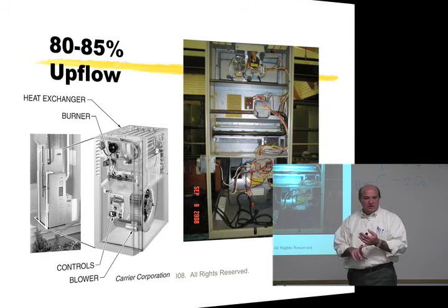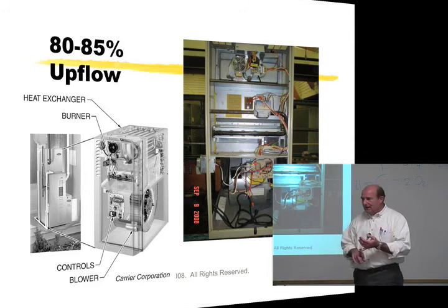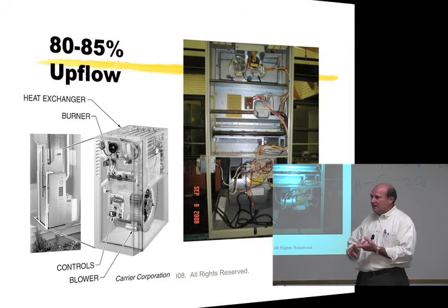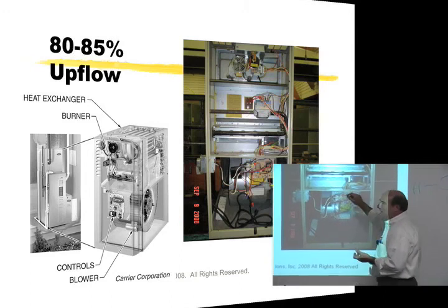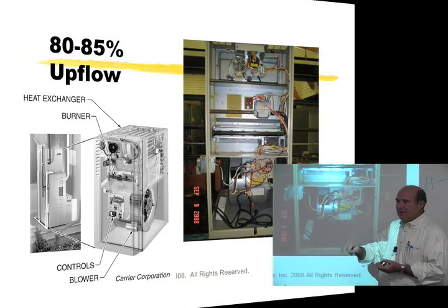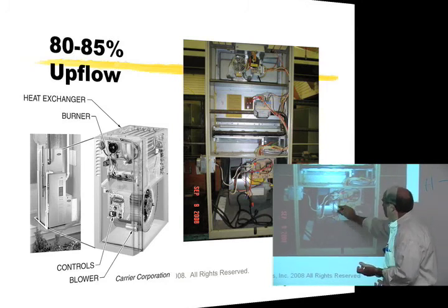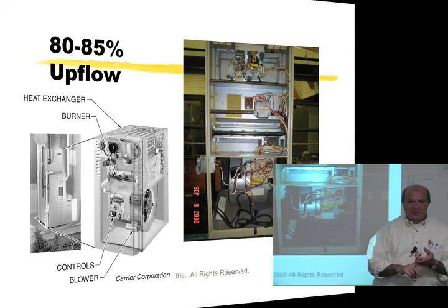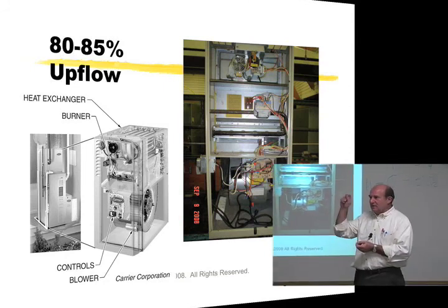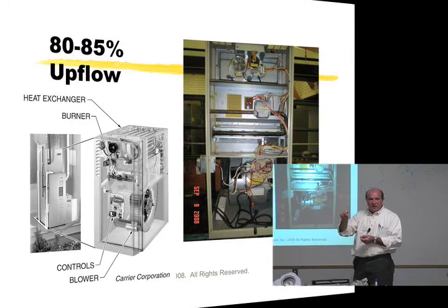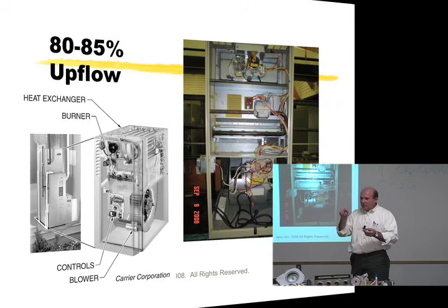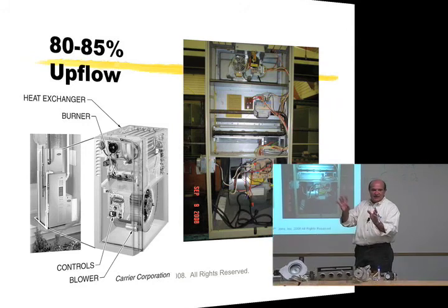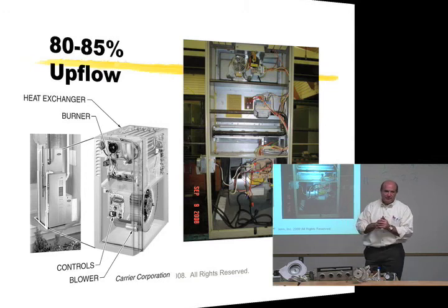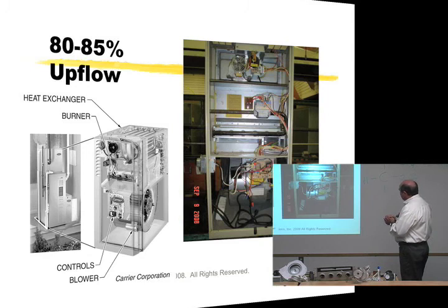Typically 4-speed motors. Some are only 3, some are 5, but you'll almost always see the black lead parked on the cooling terminal on this board. And they'll be labeled. The board will label where you see the blower motor leads come in. You can follow them right from the blower motor to the wiring harness over to wherever it ties in on the board. And it'll mark cool and heat. And so typically you'll see the black one over here on cool and maybe the yellow one on heat. And then the other two are either parked on spare terminals on the board that don't connect to anything, or they're wrapped with electrical tape or something so that they don't inadvertently short out on something, because there's always induced current through those things.